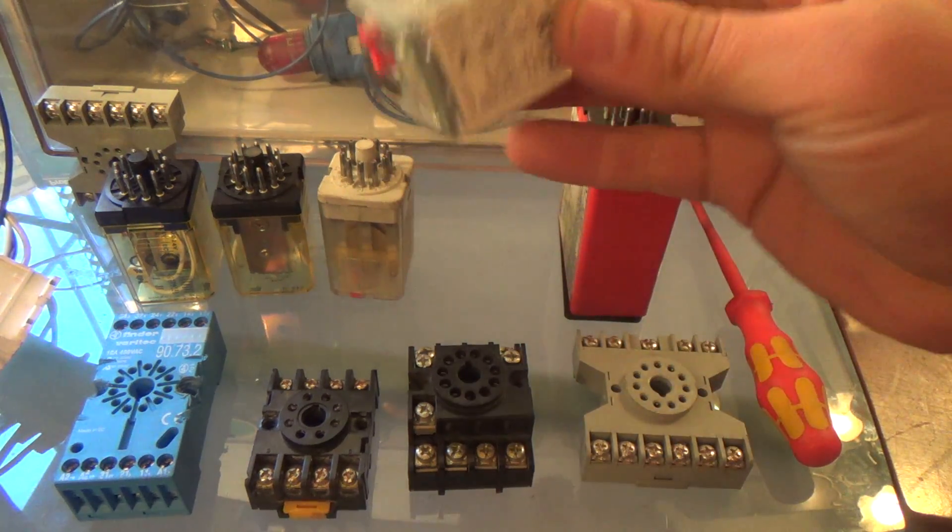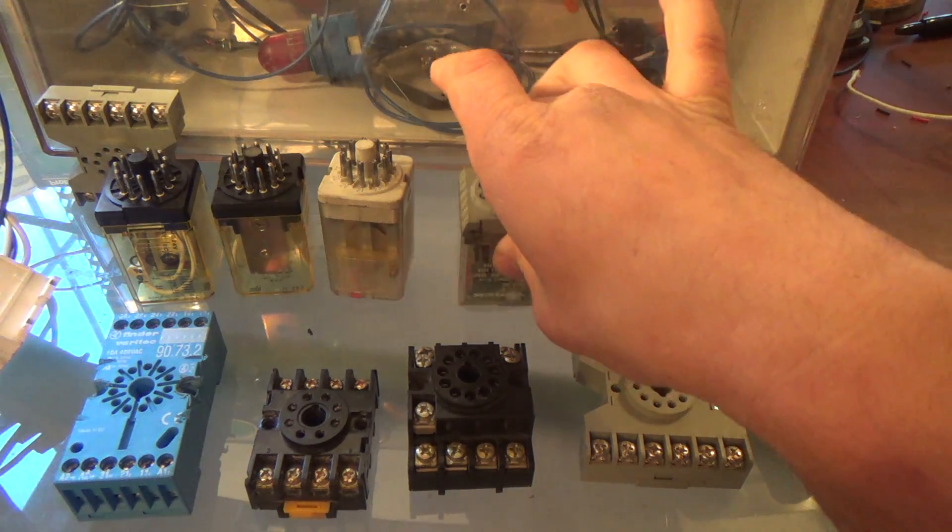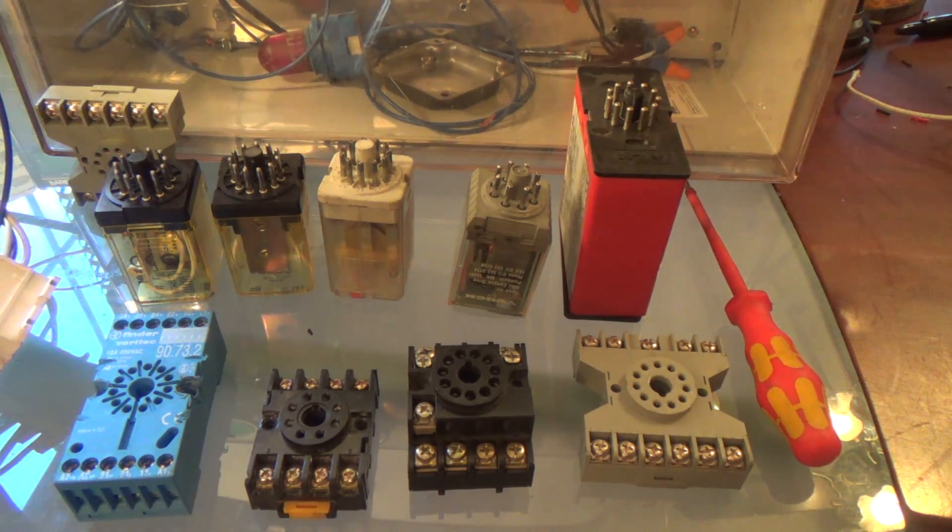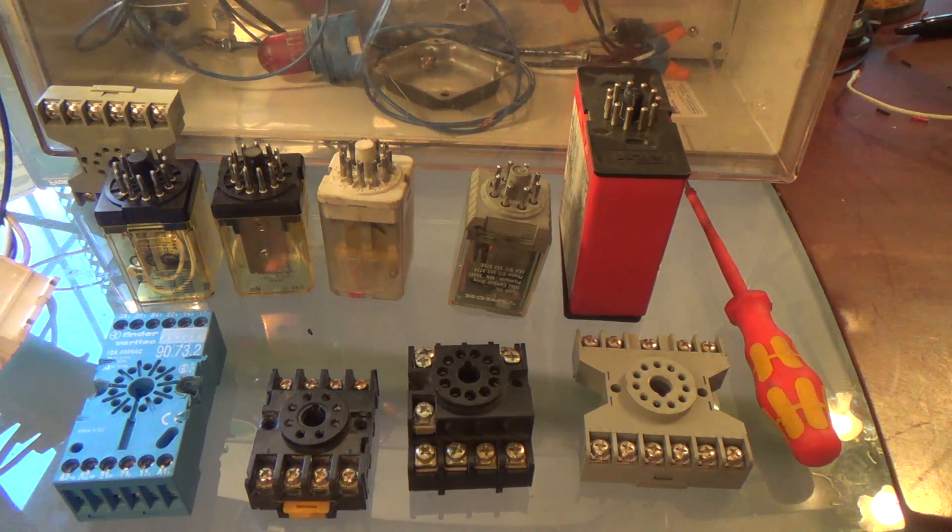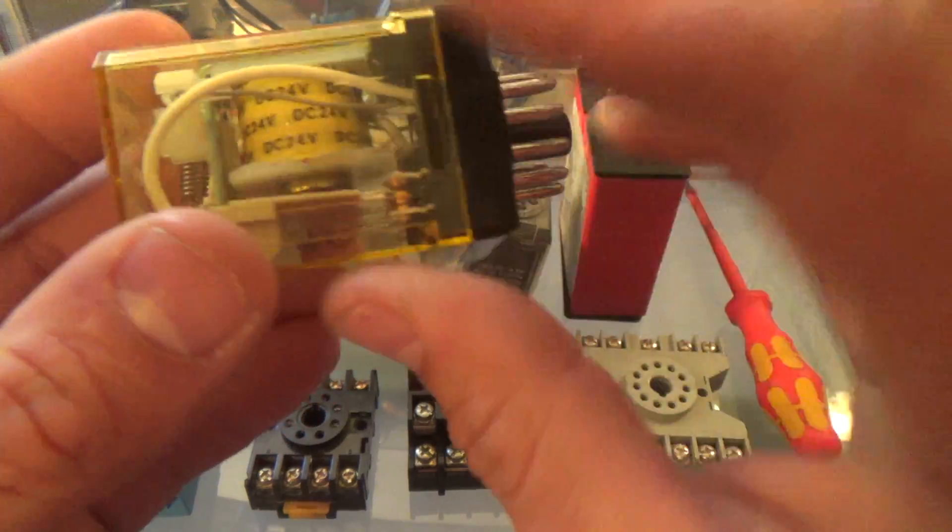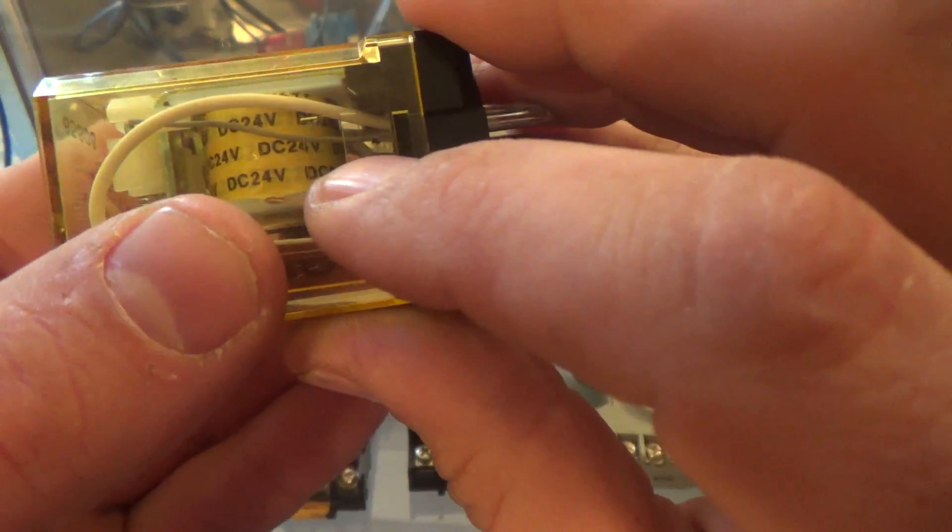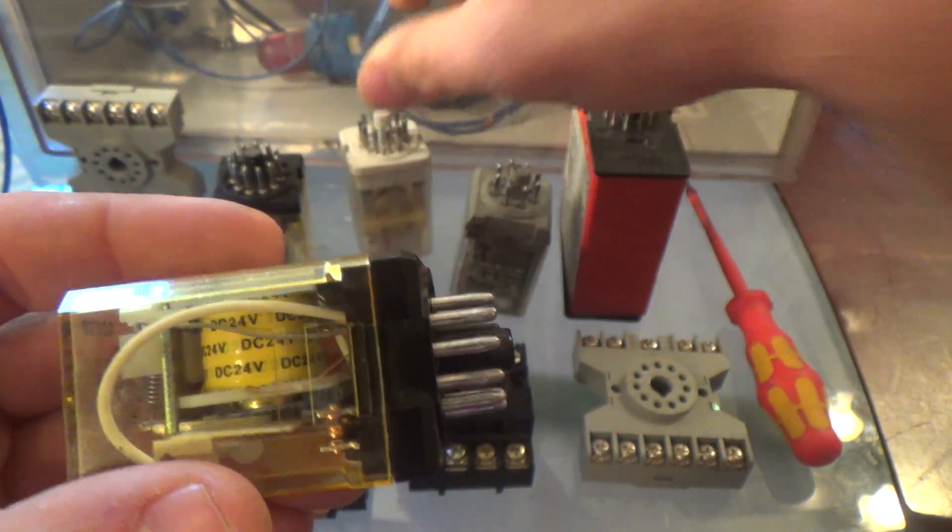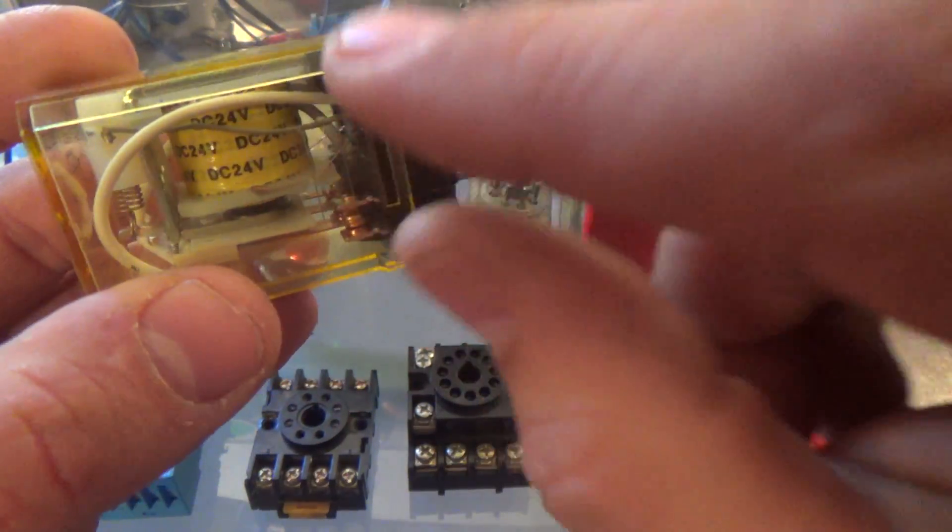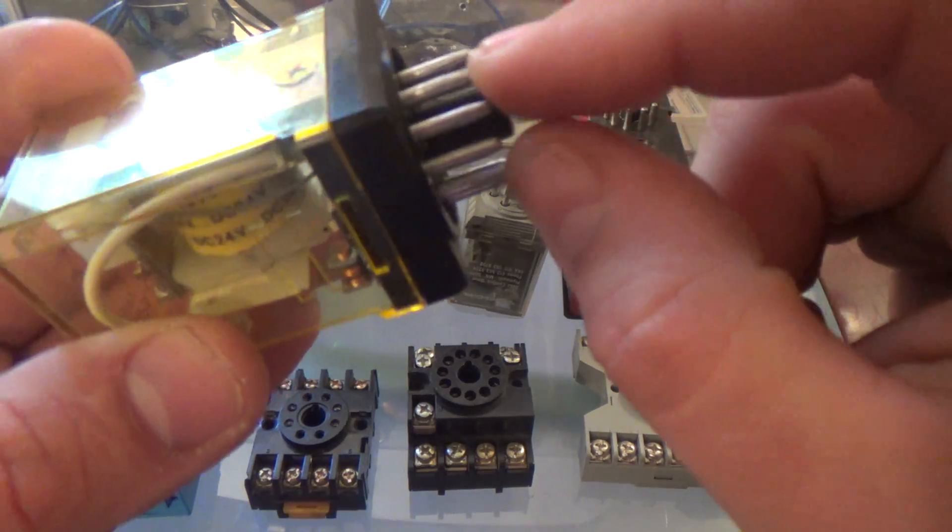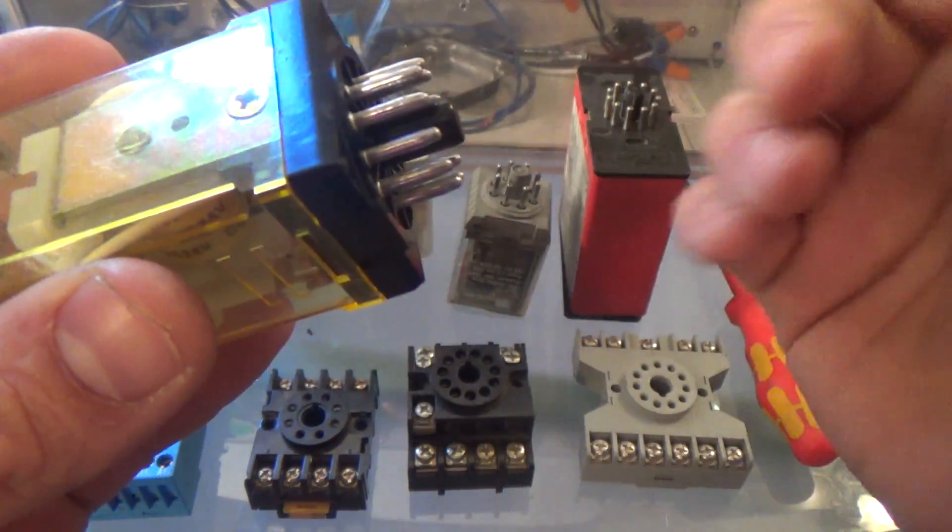They all have a little schematic on the side. They all go into a certain block and you wire them up based on what you need, based on their schematic. So let me show you that. Here is a nice relay - the manufacturer was nice enough to put the coil voltage on the coil, that's very smart. Some of these not so lucky. So 24 volts - put 24 volts on the coil, the contacts that are in the ice cube relay will change state.